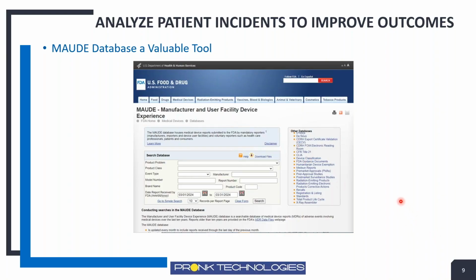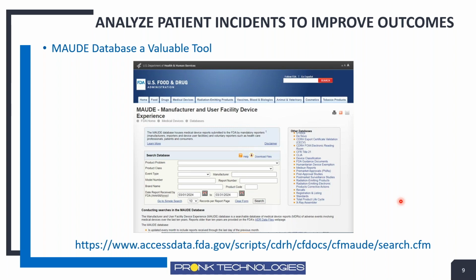Great. So you could see quite a number of tests to do on a ventilator, as I'm sure you have done many, many times. We want to cover a couple other tools that we think could be beneficial as we're servicing ventilators. One is having access to the MAUDE database. It's a database available to us all. There's a link here at the bottom that lets you see any incidents, any issues reported on any kind of FDA regulated device out there. So this allows us to look at incidents reported to the FDA, any machine failures on any kind of device. It could be a really helpful tool if you're trying to investigate or considering purchasing ventilators for your facility, to see what the history has been service-wise.